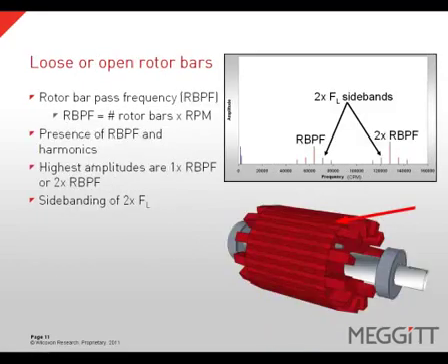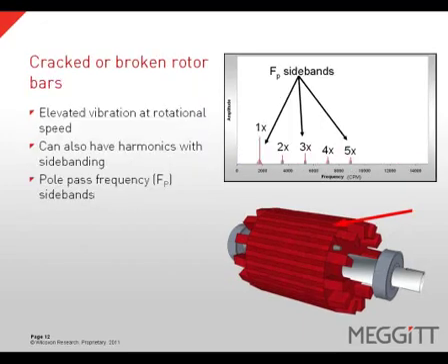Loose or open rotor bars will generate rotor bar pass frequency and possible harmonics in the spectrum. The highest amplitudes are typically at one-times or two-times rotor bar pass frequency. It is also very common to have sidebands around the rotor bar pass frequency spaced at two-times line frequency. Cracked or open rotor bars will cause elevated levels of vibration at running speed and possibly at its harmonics, with sidebands around the rotational speed harmonics spaced at pole pass frequency.